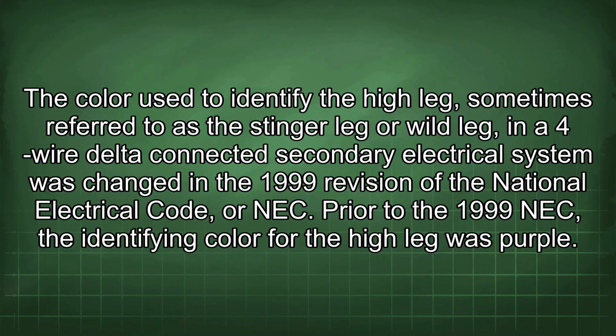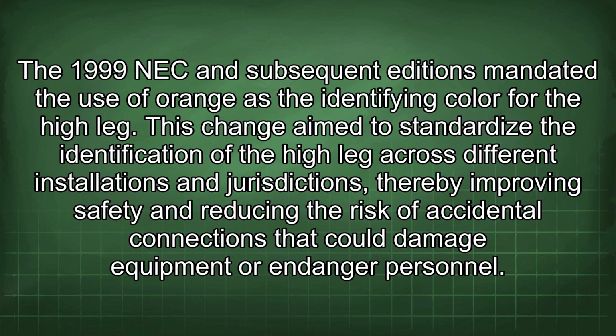The color used to identify the high leg, sometimes referred to as the stinger leg or wild leg, in a 4-wire delta-connected secondary electrical system was changed in the 1999 revision of the National Electrical Code, or NEC. Prior to the 1999 NEC, the identifying color for the high leg was purple. The 1999 NEC and subsequent editions mandated the use of orange as the identifying color for the high leg.